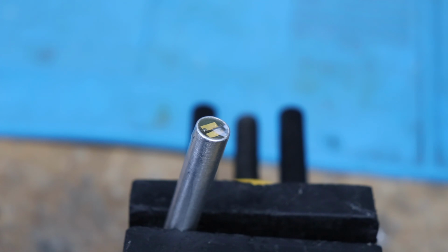Now those square things that you can see, there's two of them. Those are actually the piezoelectric crystals. I think the older machines might have used quartz, but I think these ones are made of a special piezoelectric ceramic, which I believe is called PZT, a mixture of various oxides of various metals, which has better piezoelectric properties than quartz.